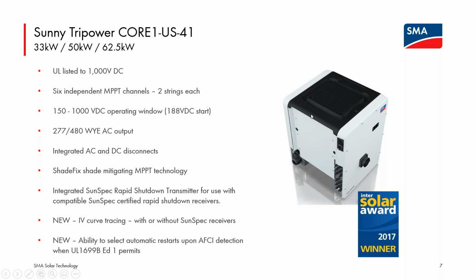In addition to the wide voltage range, the DC inputs of the inverter are broken up into 6 independent tracking channels. So each CORE1 US-41, it's as if you're getting 6 inverters in each box. Each tracking channel is managed independently by the inverter. So that means you can have different operating voltage points for each of the 6. So you can have different string lengths, and you can have different orientations for those inputs. And since there are only 2 string inputs coming into each independent tracking channel, no overcurrent protection is needed on the input side. So there is no space for fusing here behind the DC disconnect lid.